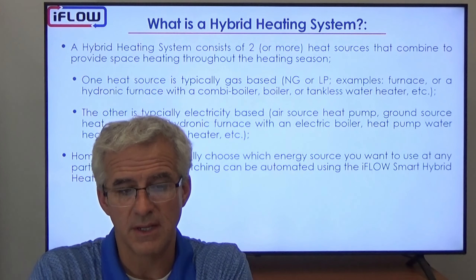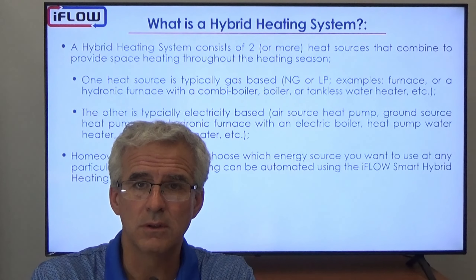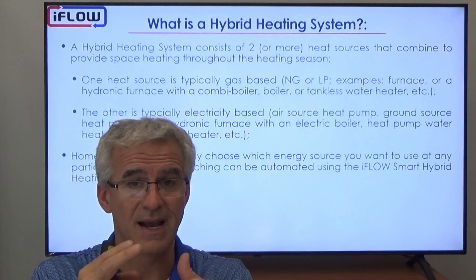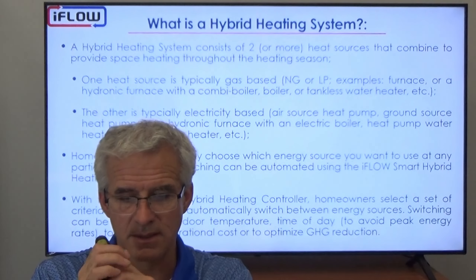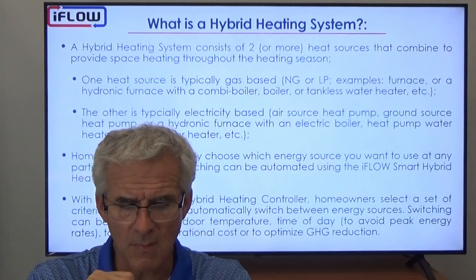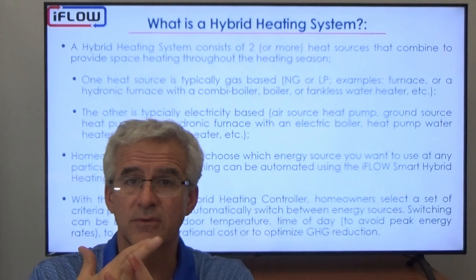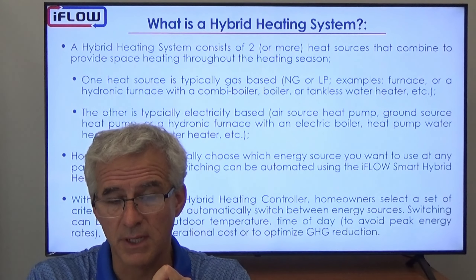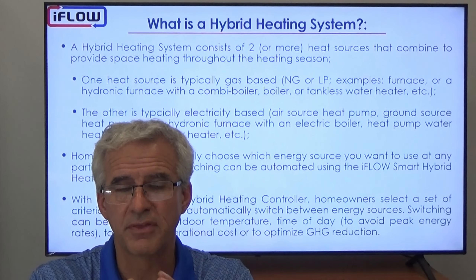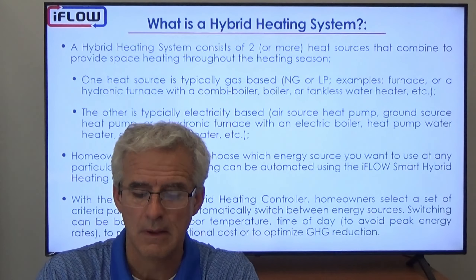Perhaps the homeowner would want something that switches automatically. In that case, we have a product called the iFLOW Smart Hybrid Heating Controller, where we connect the gas side and the electric side to the switching controller. We enter parameters to decide how we switch between them, and then switching happens automatically. Homeowners select criteria parameters on the smart controller, and it will switch based on outdoor temperature, time of day to avoid peak rates, to minimize operational costs, or to optimize GHG reduction.